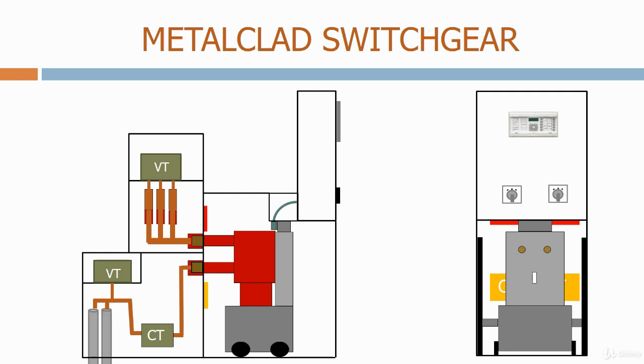Let's now add some cables onto the cable chamber and close the circuit breaker. As we can see, a circuit has now been formed, and current flows from the bus bars, through the circuit breaker, through the CTs, and onto the cables. Once the circuit breaker has been closed, mechanical interlocks ensure that it's impossible to withdraw the truck.